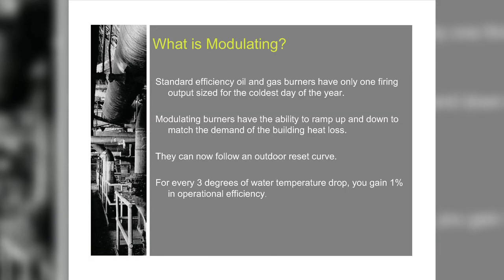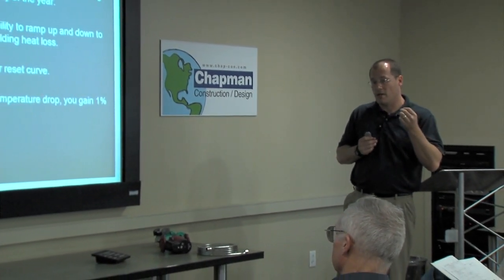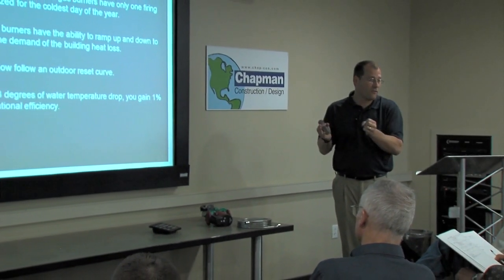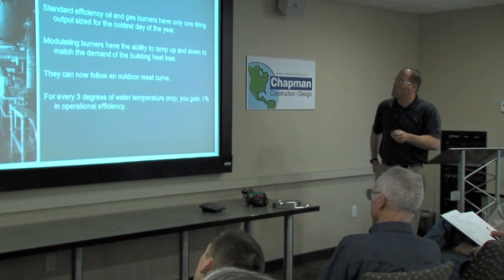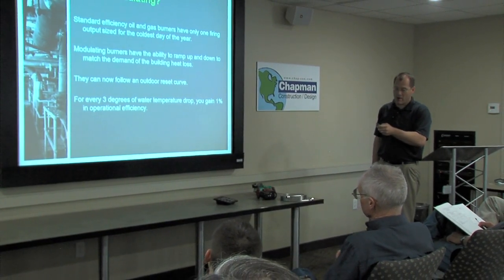We talked about what is modulating. Standard efficiency equipment fired, and it was sized for the worst day of the year. So if it was a 1,000,000 BTU boiler, when it fired, you got 1,000,000 BTUs. Modulating now says if you only need 100,000 BTUs, then we're going to slow our fan down, slow our fuel intake down, and we're going to only give what is needed. So that's really what the term modulating is talking about, speeding up and slowing down that firing rate.